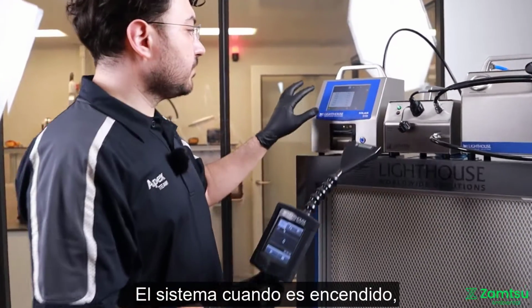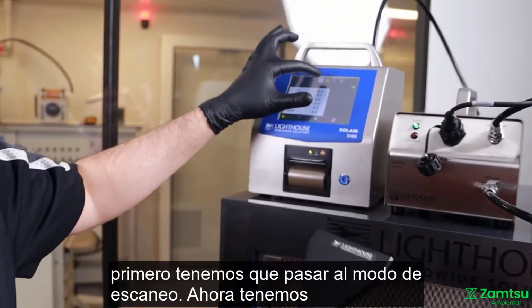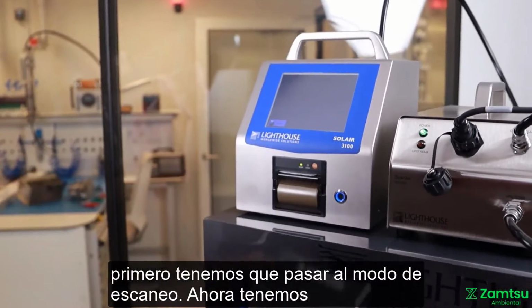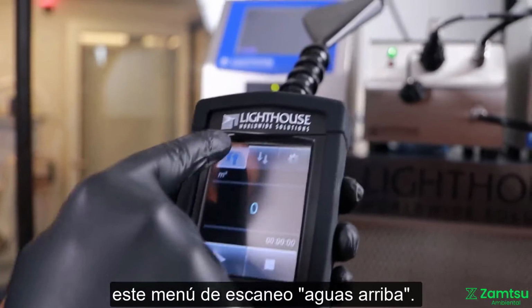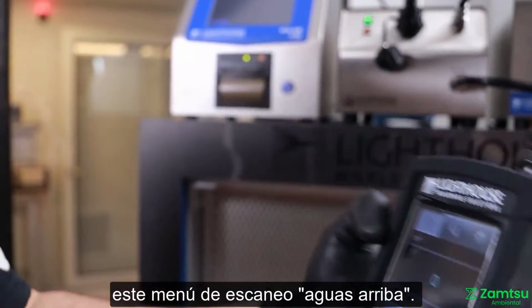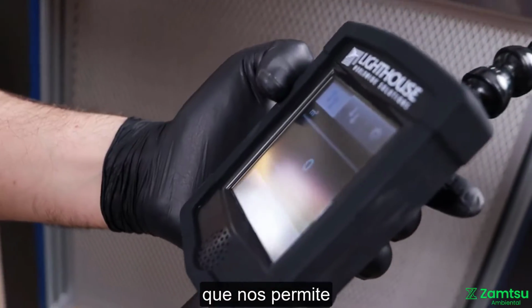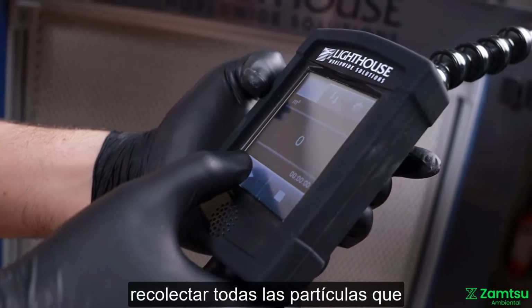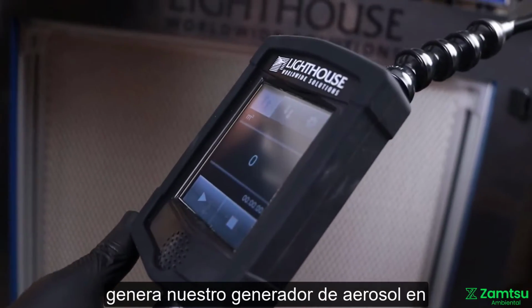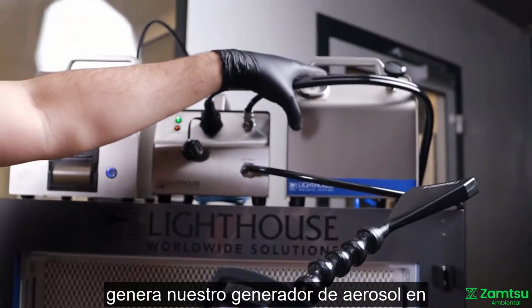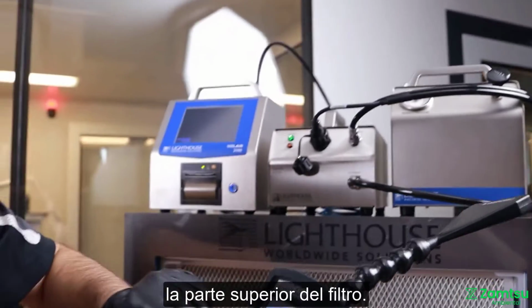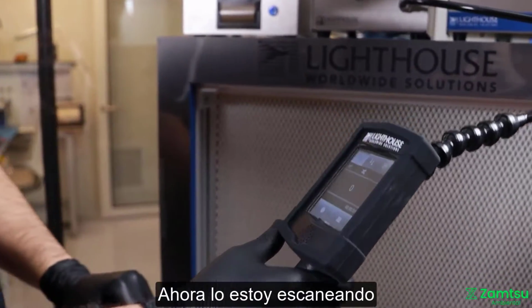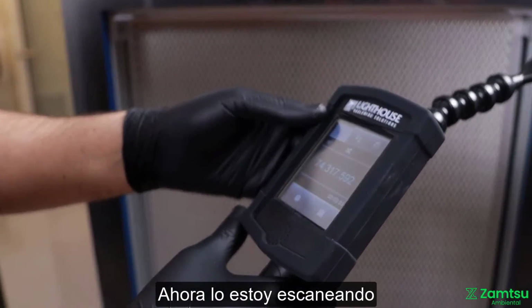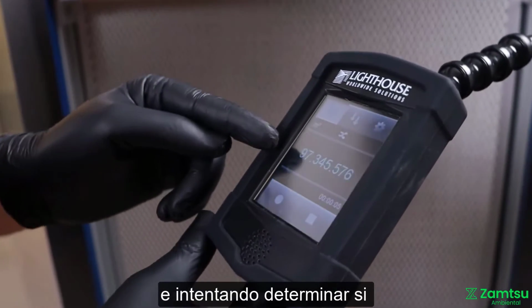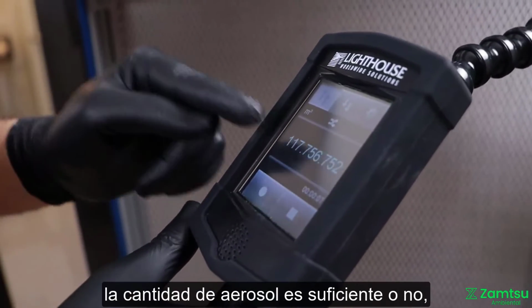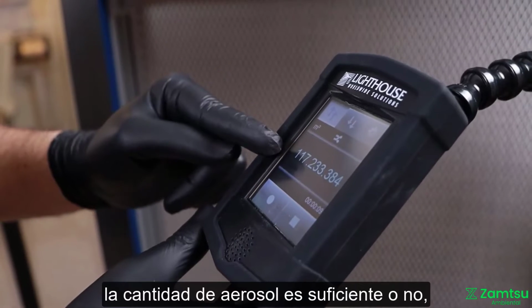So the system, when we turn it on, we have to move into scan mode first. Now we have this upstream scanning menu. This upstream scanning menu allows us to collect all the particles that are generated by our aerosol generator to the upstream of the filter. Now I'm scanning it and trying to understand if the aerosol is enough or not.